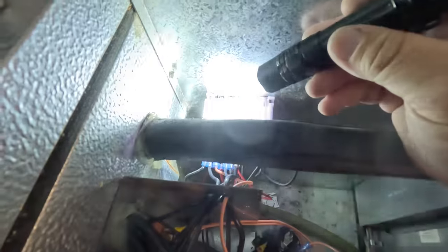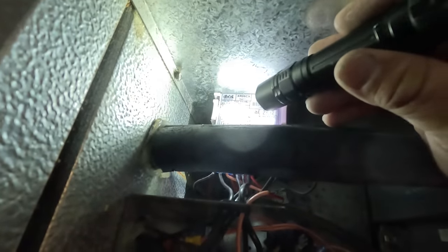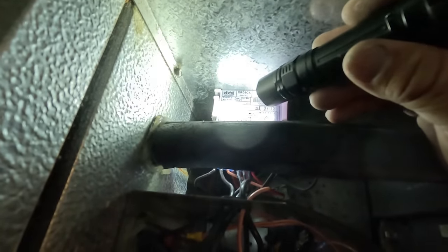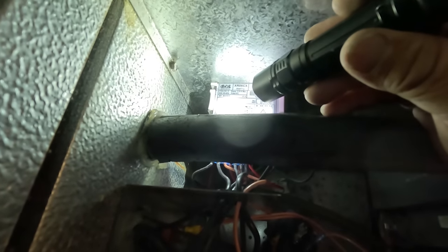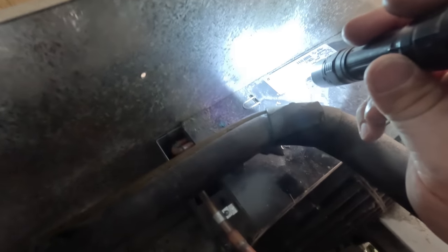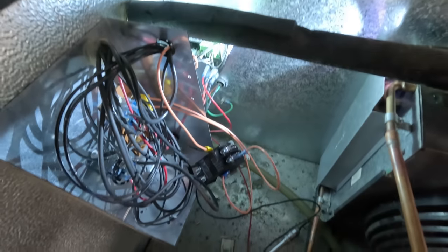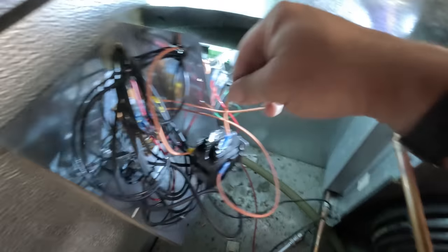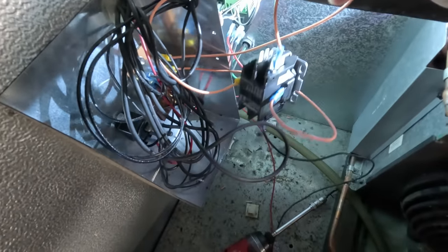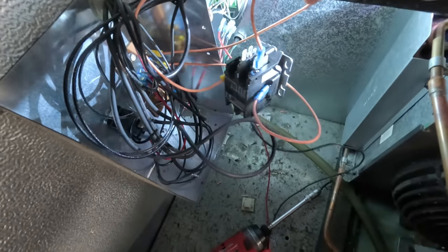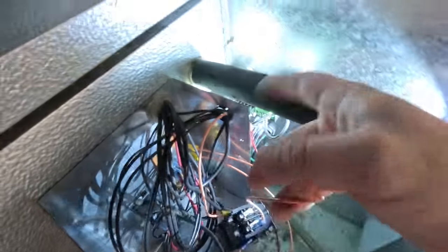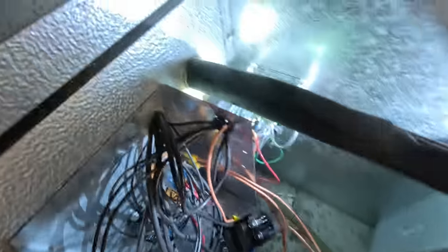I did hook the fan back up to the original spot. The fans are not rated for a whole lot, as you can see right there. The maximum current on this thing is 16 amps, 5 amps for the fan, which leaves you about 11 amps for the compressor. That's why I don't like that. Rated load amps is 8. I mean, yeah, it's minimum circuit ampacity, 11. So I mean, it's a smaller compressor, but still it's going to make it last longer. It's cheap insurance. If there's a short in the compressor, which this compressor was replaced, I don't know how long ago, I think two years ago, this is going to take care of any shorts. It's going to burn up a 20 some dollar contactor versus several hundred dollars controller.